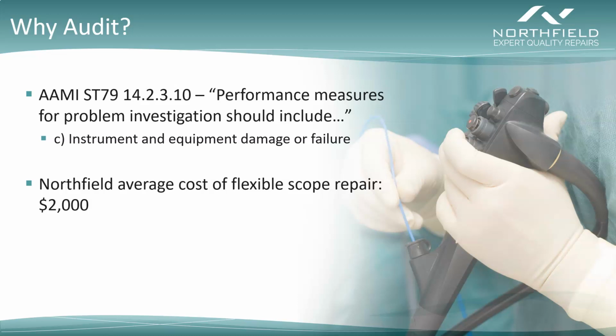Now, because of the importance of auditing and because of the value that it can bring to you, Northfield Medical has designed audit forms that you can use to help evaluate your process and identify where those sources of preventable damage are occurring. And those audit forms are available for free upon request. We designed the audit forms to follow a single device through one cycle of its life. Therefore, you'll want to have one audit form for each time the device is used, and you'll want to follow it throughout its entire process.